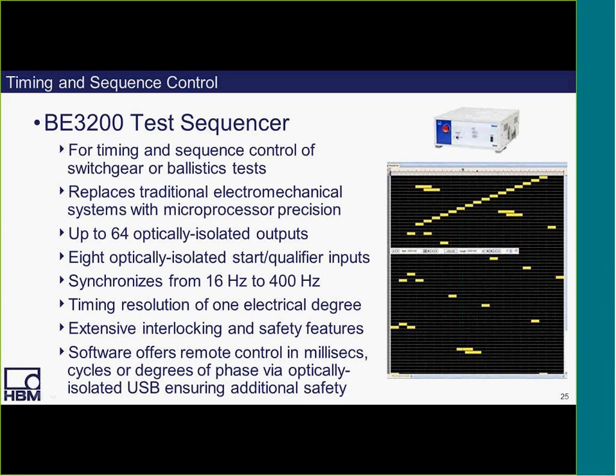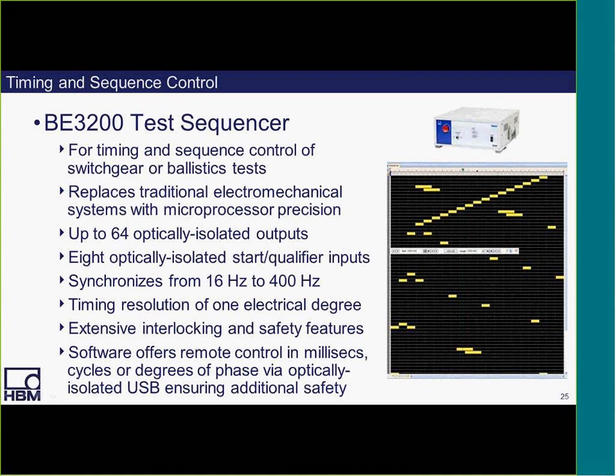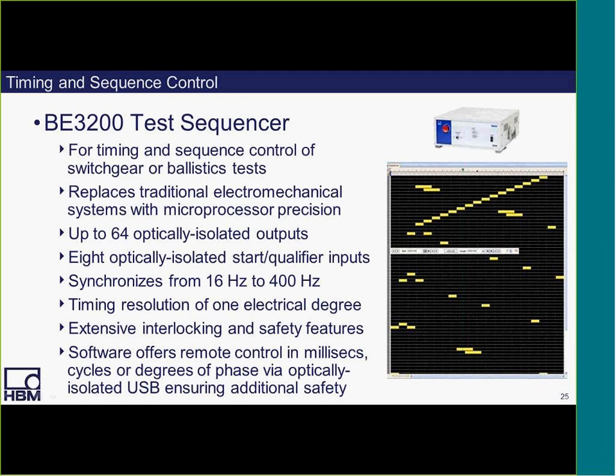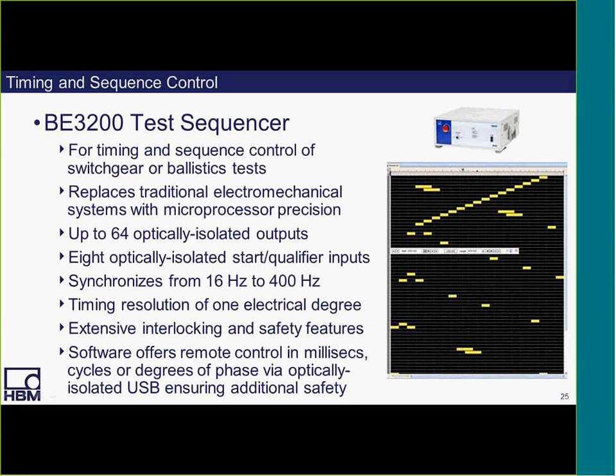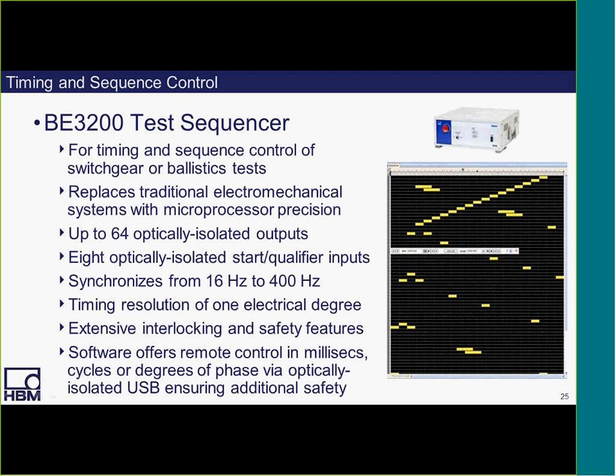Now, a device called a test sequencer is often used to control the operation of a test sequence for switchgear or ballistic tests. In fact, this digital BE3200 test sequencer shown at the top right replaces the traditional electromechanical systems with microprocessor precision. It offers up to 64 optically isolated outputs and 8 optically isolated start qualifier inputs.